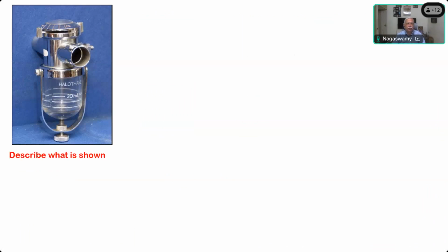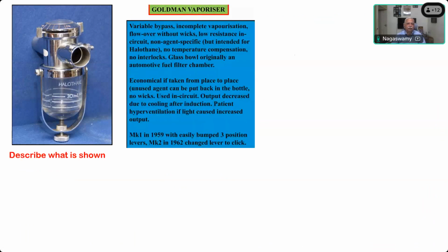Describe what is shown here. Halothane vaporizer. The Goldman Hamilton vaporizer. Correct. Somebody is mumbling; it should be loud. Okay, this is a Goldman vaporizer. It is a variable bypass, flow-over, incomplete vaporization vaporizer, with low resistance inside the circuit, so usage inside the circuit can be done. It is non-agent specific, but by practice usually used only for halothane, though you can use any agent you want. No temperature compensation, no interlocks, and the glass bowl was originally an automotive fuel filter chamber.